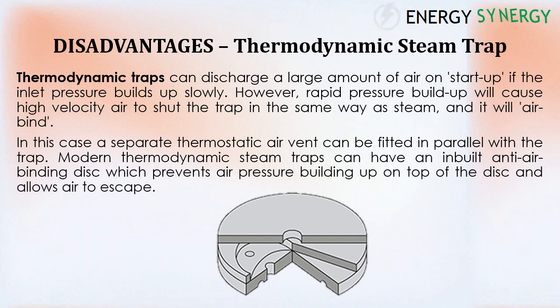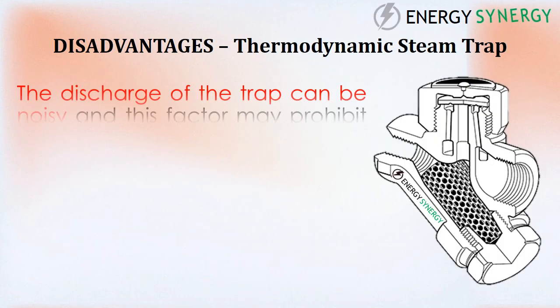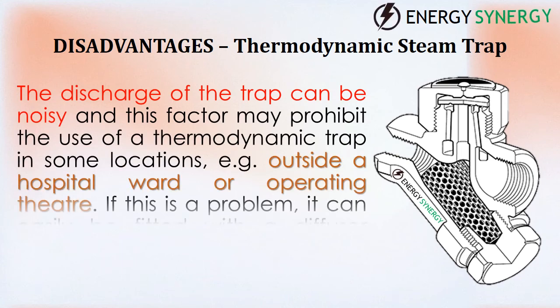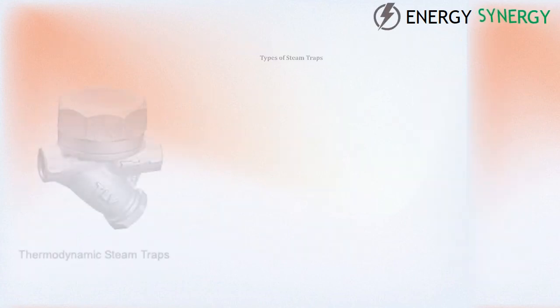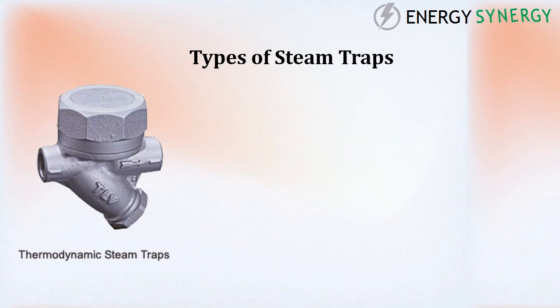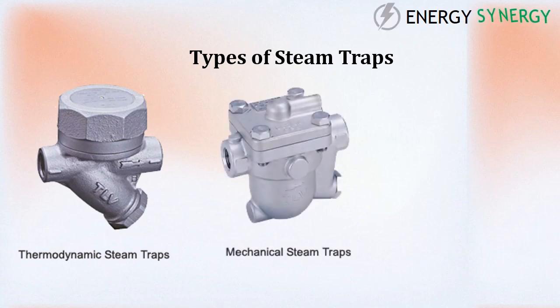Modern thermodynamic steam traps can have an inbuilt anti-air-binding disc which prevents air pressure building up on top of the disc and allows air to escape. Another disadvantage is that the discharge of the trap can be noisy, which may prohibit its use in some locations — for example, outside a hospital ward or operating theater. If this is a problem, it can easily be fitted with a diffuser which considerably reduces the discharge noise.